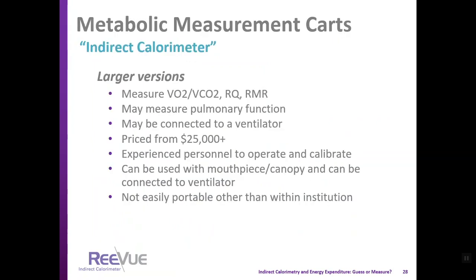Indirect calorimetry measurements are made using an indirect calorimeter or metabolic measurement cart. These larger versions measure oxygen consumption, CO2 production, respiratory quotient, and resting metabolic rate, and may also measure pulmonary function. Many are connected to or are a component of a ventilator. They are expensive, require experienced personnel to operate and calibrate, and are generally not very portable.